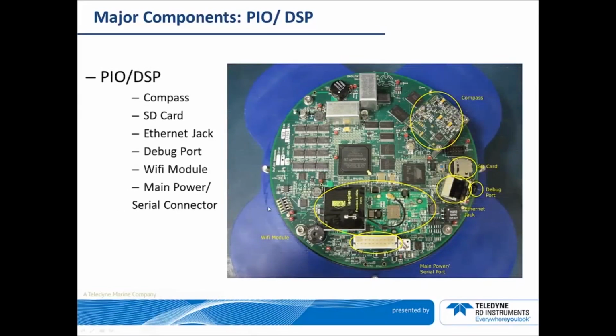The PIO DSP board contains important components, such as the compass and the micro SD card. For workhorse users, you will note that the workhorse uses up to 2 PCMCIA cards for a maximum size of 4 GB total. The Sentinel V uses a micro SD card with a memory of 16 GB. There's also the debug port, which is this, and the Ethernet jack. These are normally used by RDI personnel for debugging and troubleshooting purposes. There's the wireless module. And finally, there's the main power and serial port.